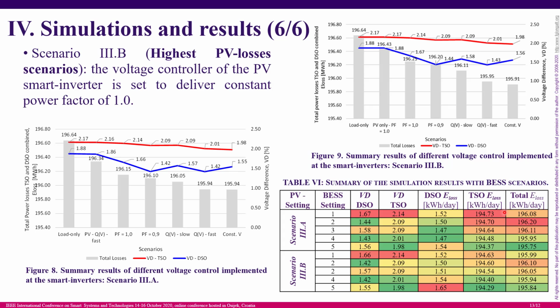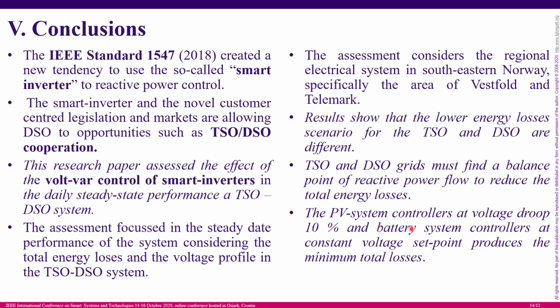And as you can see over here, the TSO energy losses don't change so much compared with the energy losses at the distribution system. The battery energy storage system provides some support for reactive power. However, because the batteries are also providing some active power local production, that has an effect on the voltage profile and the active power losses.